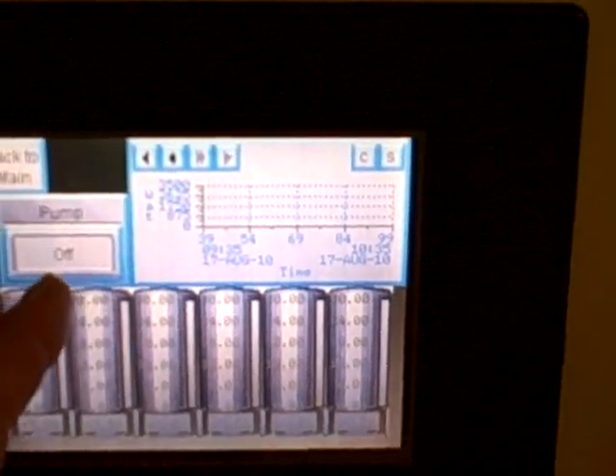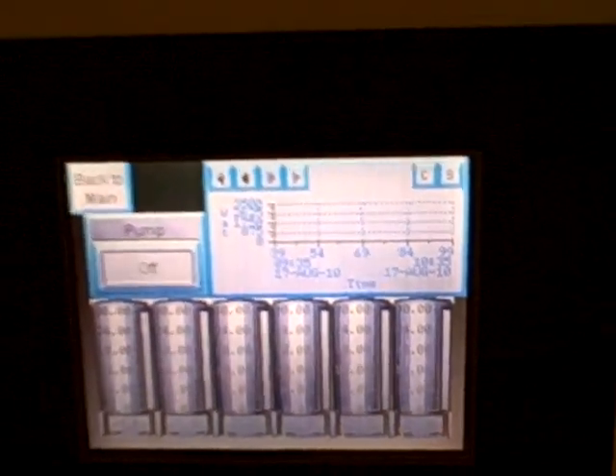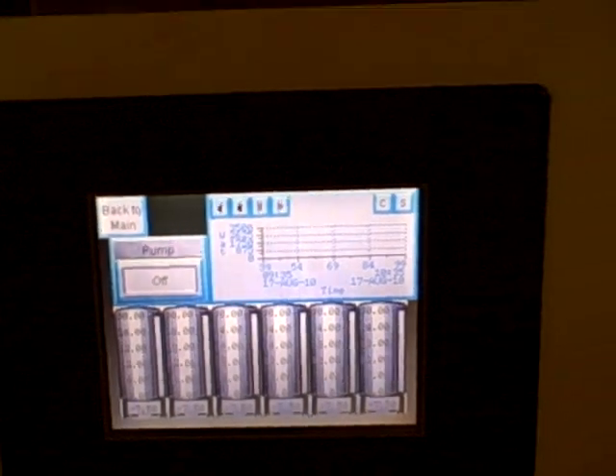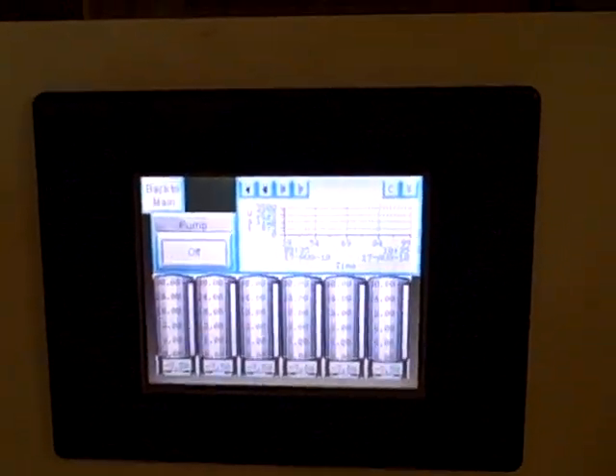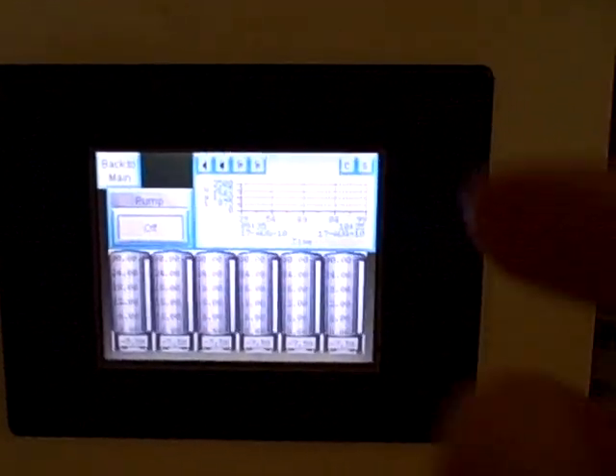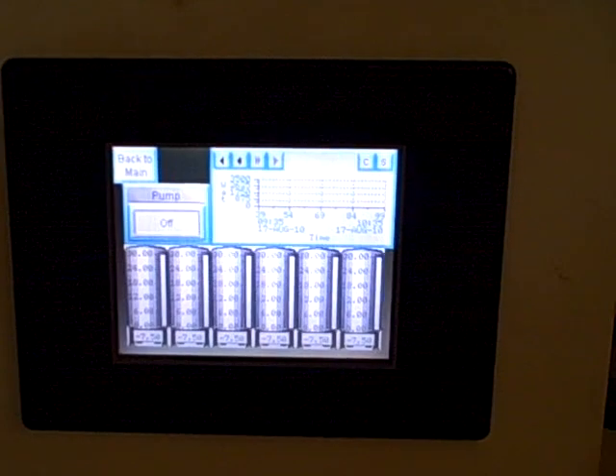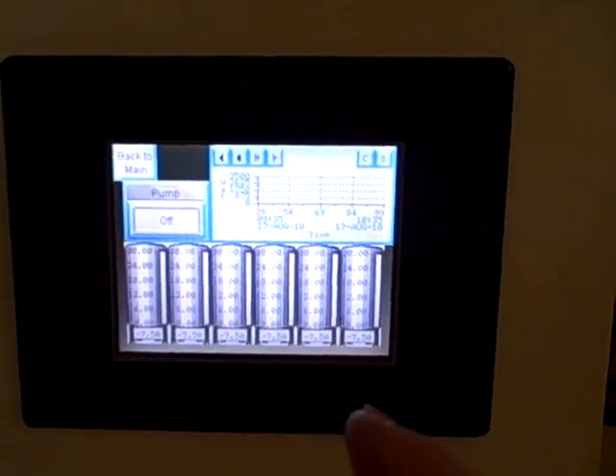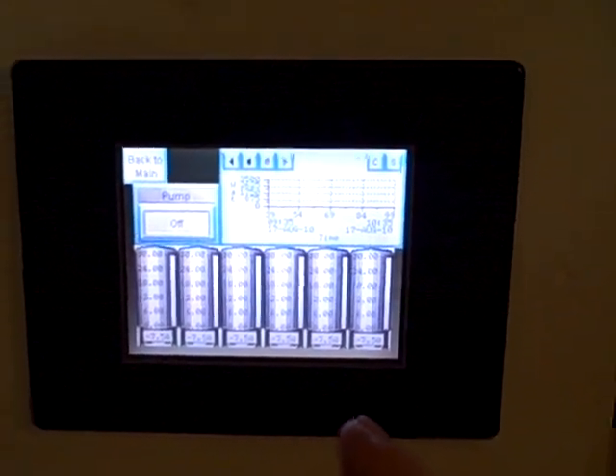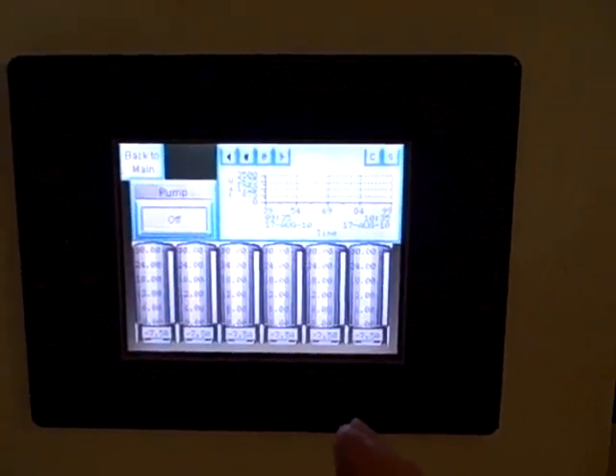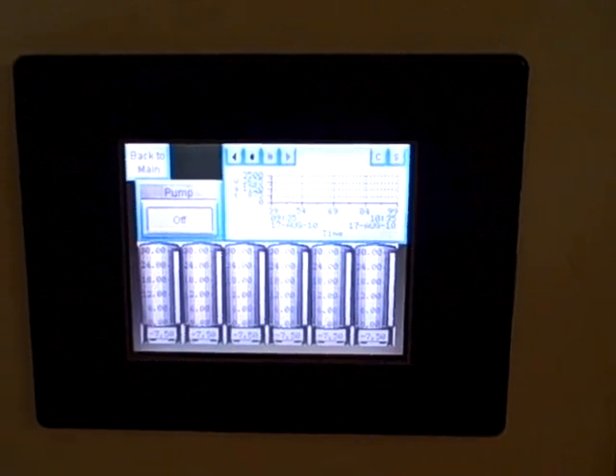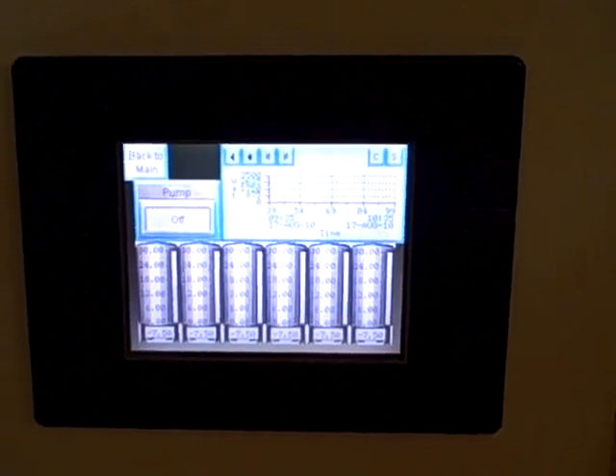But it also has a pump on it, a submersible pump in one of these rainwater tanks. We can turn that on using a push button. So I've got it set up so if you push the push button next to the water storage tanks, the PLC measures the time that you've held the button down and then runs the pump for 100 times that amount of time you held the button down.